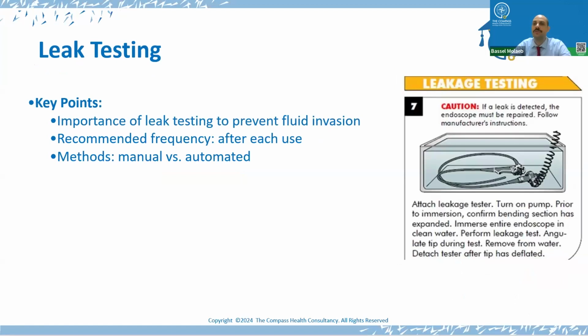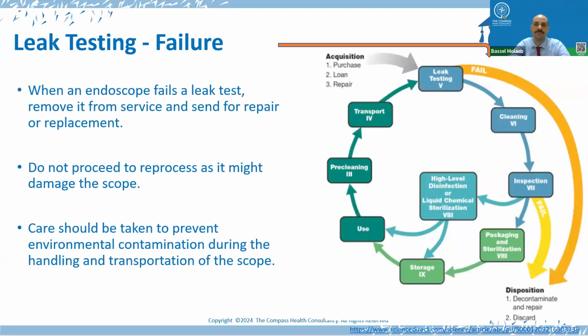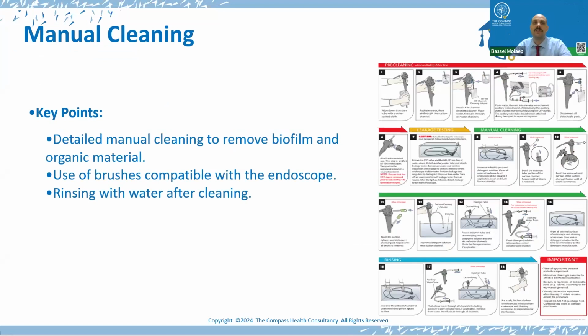It should be performed after each use and before use of a new, repaired, or loaned endoscope. Leak testing must be done in accordance with the endoscope and leak testing equipment IFUs, whether it is done by the automated method or the manual method. So what happens if you have a leak testing failure? You need to remove it from service and send it for repair or replacement. You should not proceed to reprocess it, as it might damage the scope. And you should be careful to prevent environmental contamination during the handling and transportation of the scope after failing the leak test.